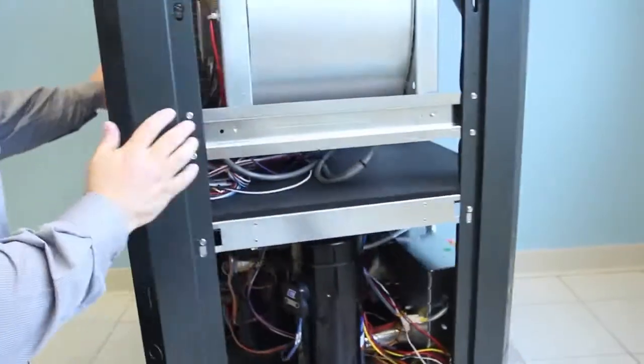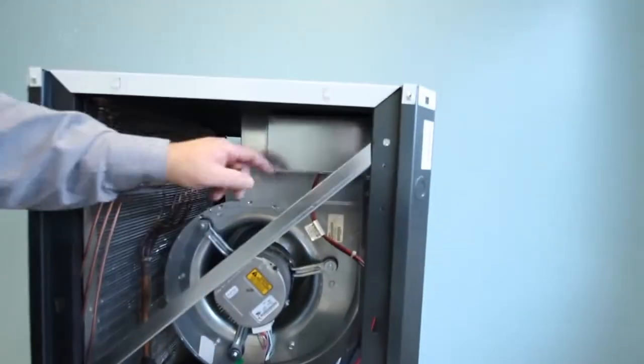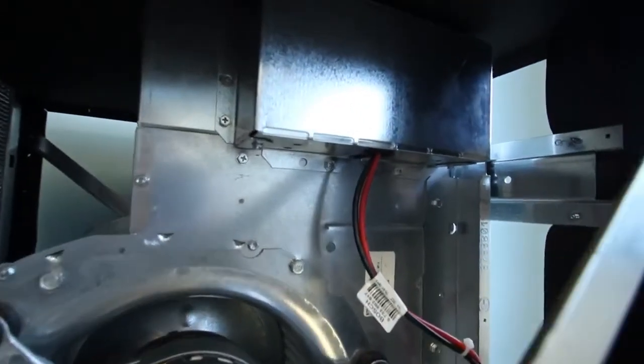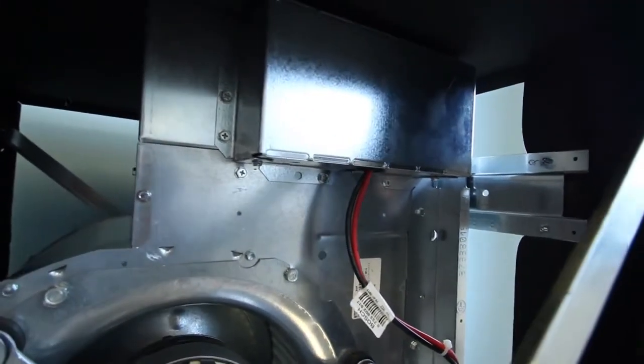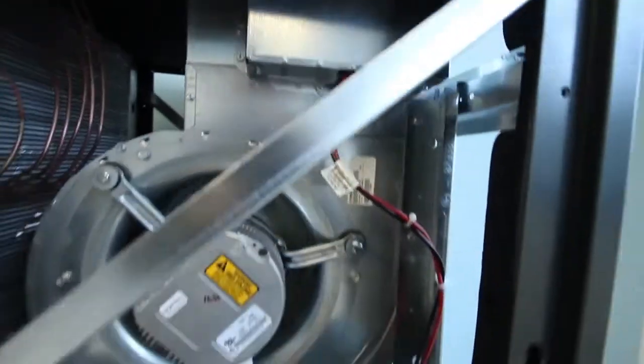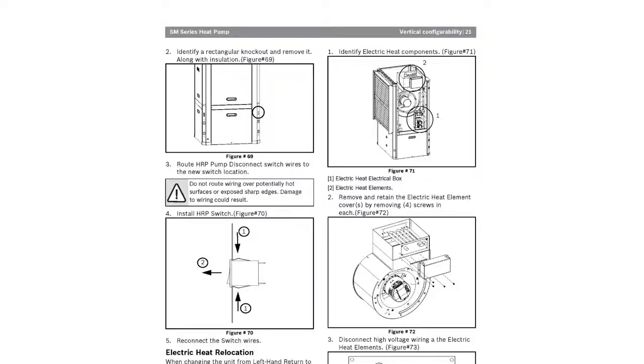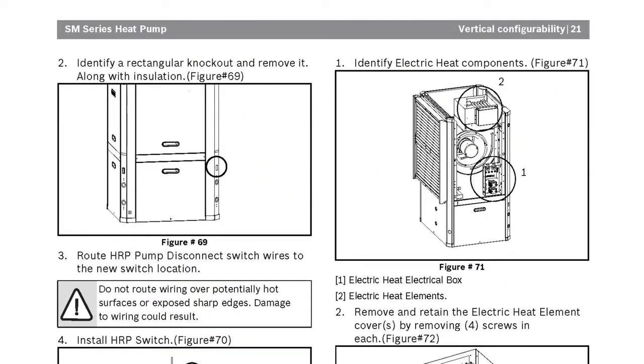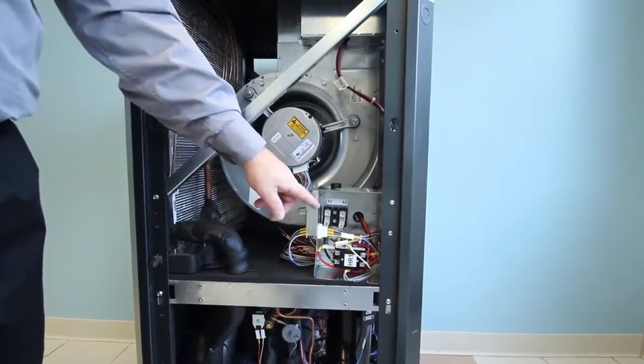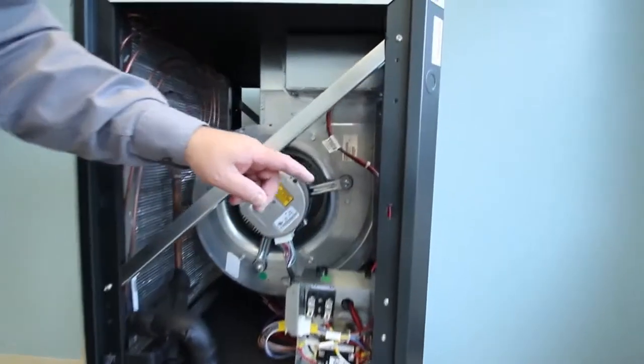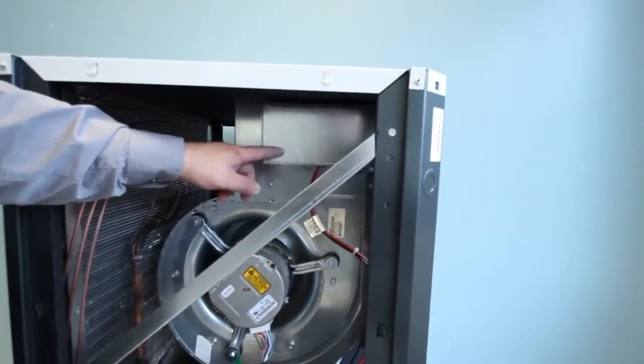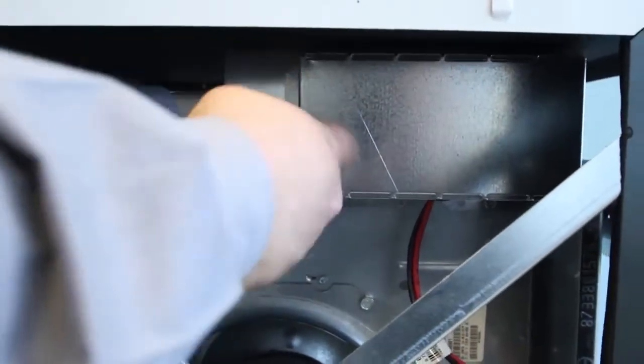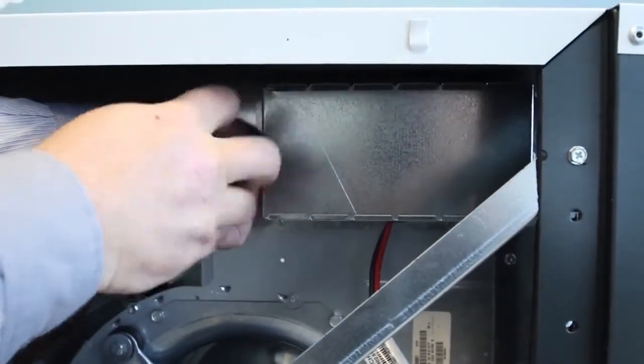Because we have the internal electric heat option installed on this unit, there is a third set of instructions that will need to be completed, and that is the relocation of the electric heat components. Those instructions begin on page 21 of the I&M manual. First, identify the components. They include the electric heat e-box and the electric heat elements. First, remove and retain the electric heat element cover by removing the 4 screws.